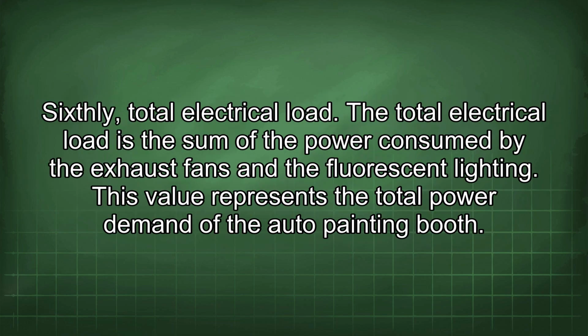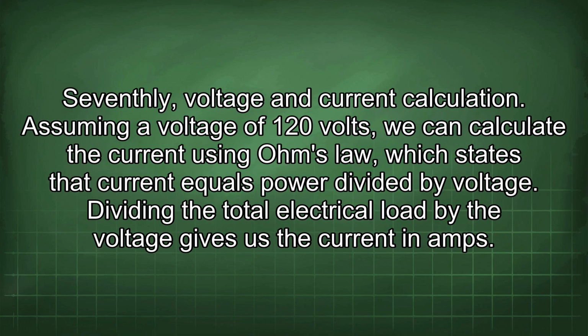Sixthly, total electrical load. The total electrical load is the sum of the power consumed by the exhaust fans and the fluorescent lighting. This value represents the total power demand of the auto painting booth. Seventhly, voltage and current calculation. Assuming a voltage of 120 volts, we can calculate the current using Ohm's law, which states that current equals power divided by voltage. Dividing the total electrical load by the voltage gives us the current in amps.